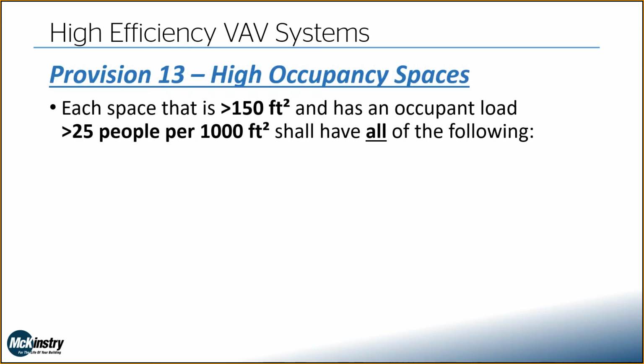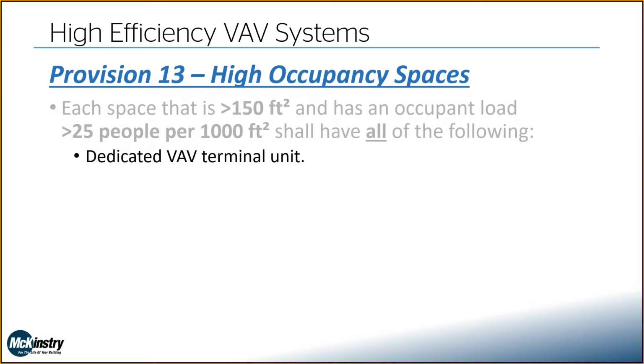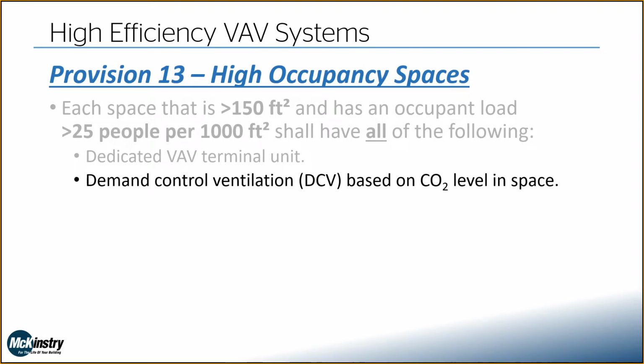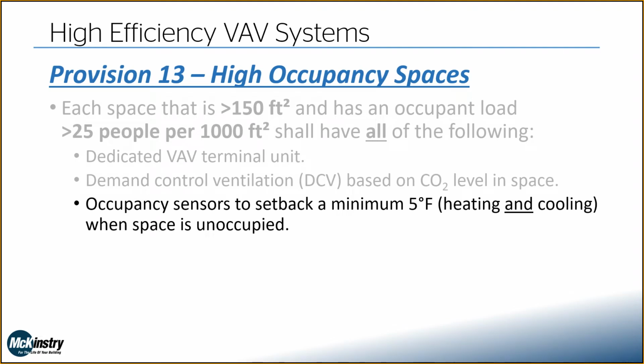High occupancy spaces. This one's pretty straightforward. So if we have a high occupancy space, greater than 150 square feet, designed for more than 25 people per 1,000 square feet, we have to do all of these things. It has to have a dedicated VAV box. We have to do demand control ventilation based on CO2 levels. And we have to tie it into occupancy sensors that will set back a minimum of 5 degrees in heating and cooling whenever that space is unoccupied.